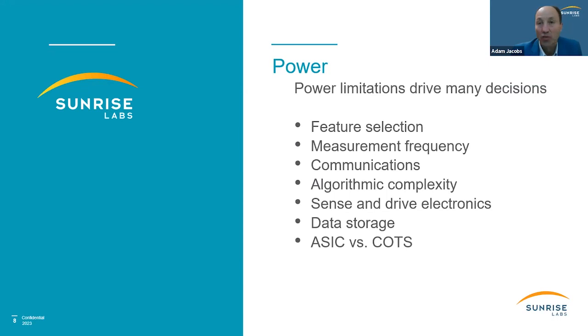The sense and drive electronics, sensing of interfaces to electrodes and driving of some kind of an impulse or a stimulation, tend to be specialized for implantable devices. For example, in a stimulation environment, you often would like to do constant current kind of driving, but it actually turns out that sometimes it's more efficient to use constant voltage. So you might choose that, even though it's not really what you would choose from a theoretical perspective.